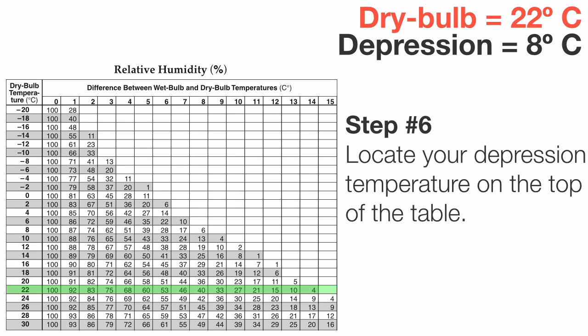Then step six, we're going to locate the depression on the top. In this case, it's eight degrees Celsius and we're going to come down. Notice we didn't really use the wet bulb on this chart. We're simply using the dry bulb, which is the same as the air temperature, and the depression, which is the difference between the dry and the wet.